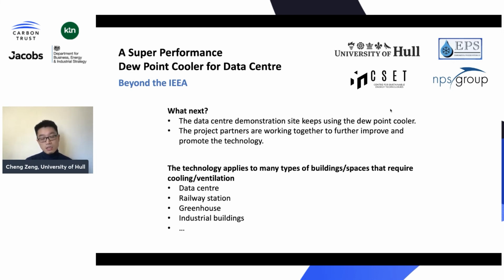This dew point cooler technology can be used in many buildings and spaces requiring cooling and ventilation, including data centers with servers producing heat, railway stations with machinery or indoor heat sources, and greenhouses. In the horticulture sector, greenhouses gather sun and create internal heat, and you want to maintain moisture or CO2 levels - our dew point cooler ventilation is a good solution.